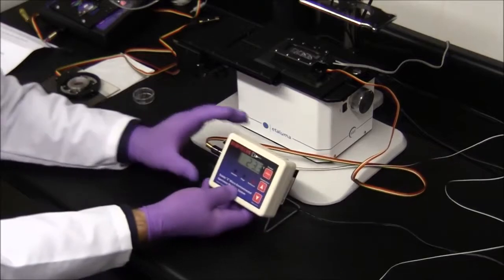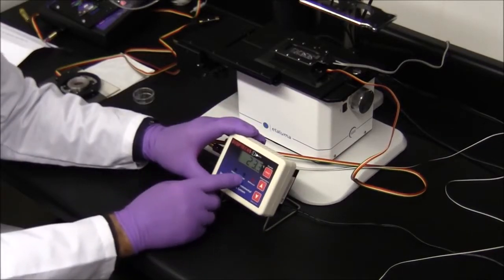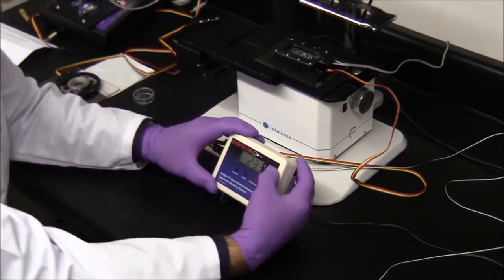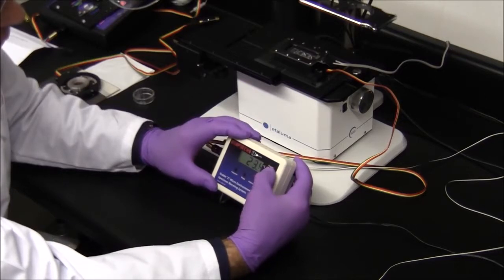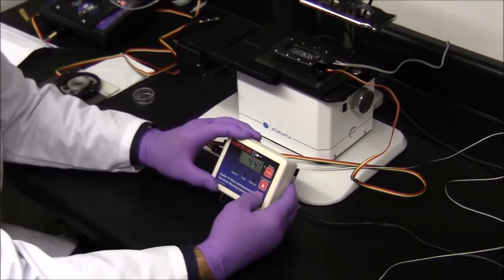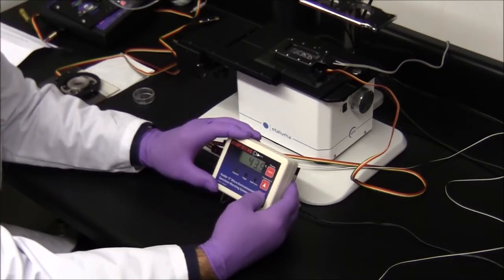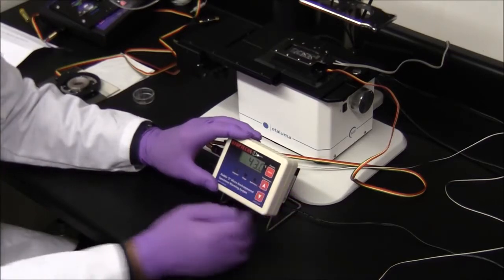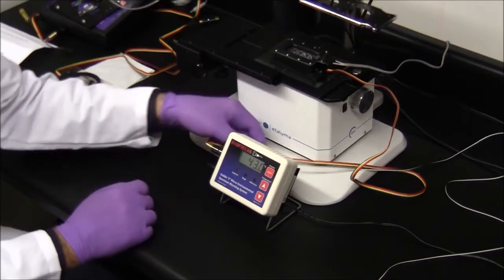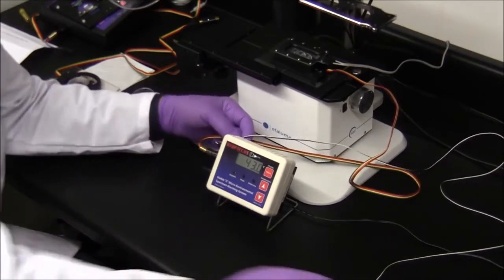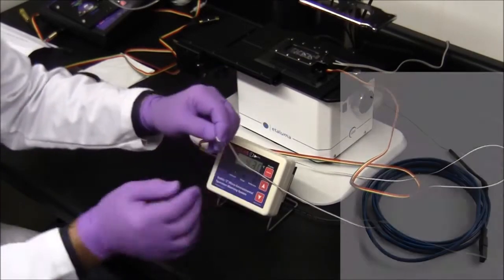The controller is powered by an AC to 12V DC wall adapter or a 12V battery. It is adjustable from ambient to 50 degrees C. The arrow keys allow you to set the temperature, and the select key cycles through the stage temperature and temperature of a reference probe provided to monitor temperatures in the chamber slide or dish.